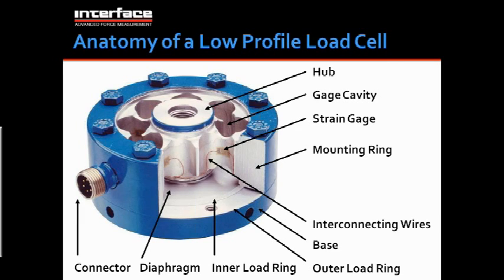A load cell could potentially have a zero shift within probably the first year of its life, perhaps. You've got to remember that it is a strain gauge, and when the manufacturer makes a load cell, you're putting a lot of stress into the metal that we're actually putting the gauges on. We exercise our load cells extensively, which minimizes those changes. So you really shouldn't see that much of a zero shift, but it could happen. If it's going to happen, it usually happens very early on in its life, and then it becomes asymptotic, and the longer it's in the field, the less the zero change will occur.